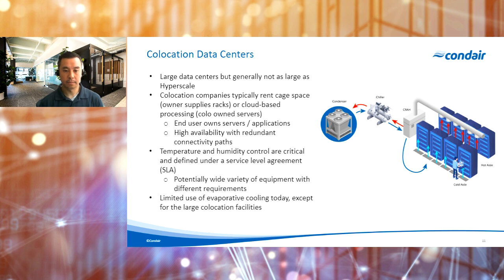So in this type of situation, given the potentially wide variety of IT equipment in the facility, temperature and humidity levels are typically operated at a much more conservative range compared to hyperscale facilities. Due to these requirements, use of direct evaporative cooling is definitely less common. While we've seen it in some of these facilities, it tends to be more common to see chilled water systems and CRAH units or CRAC units. Though when we do see facilities with CRAH and CRAC units, it's still common to see the use of either standalone humidifiers or humidifiers built into the cooling units to provide some control over that parameter.